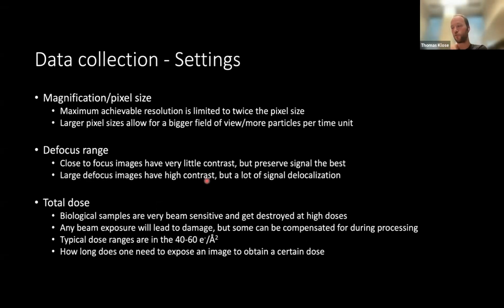From a user point of view, what you will probably be asked when you set up the microscope is what magnification you want to use. And that translates to what pixel size you will have. As Sven said in his talk, the maximum achievable resolution is limited to twice the pixel size.